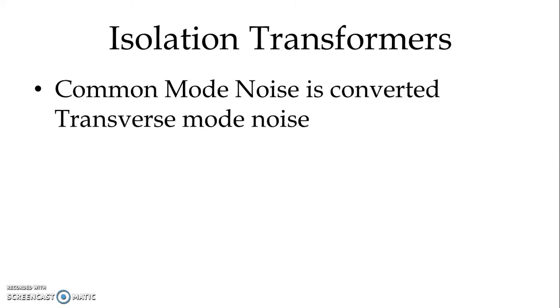Common mode noise is equally present in the line and the neutral circuit with respect to ground. Common mode noise may be converted to transverse mode noise, which is noise between line and neutral in electrical circuits, which is troublesome for sensitive data and signal circuits.